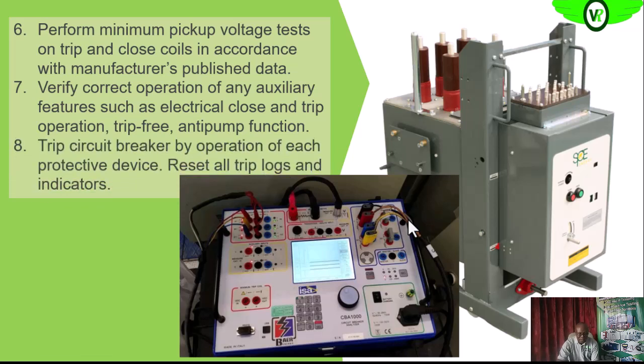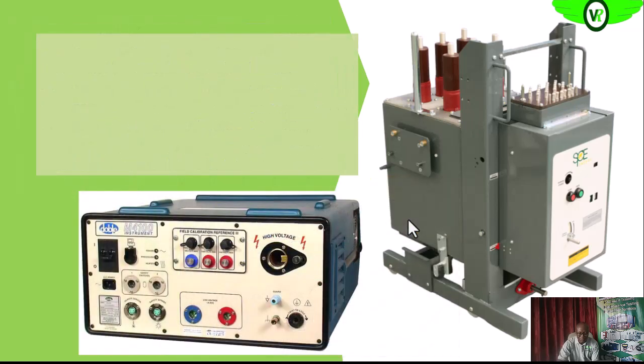Then next we can look at the trip circuit. Okay, so we want to operate the protective device to see that the trip circuit will actually respond. So all of those we can simulate some fault condition with the circuit breaker analyzer to see that the circuit breaker will actually trip when such condition is present. So the logs that we have in the protection, we can download them, and then if possible we can reset all the trips log, or we just leave them in the memory. Okay, and then if there are the ones that will prevent the equipment from functioning properly, we want to reset the equipment back to the factory, that is back to what we feel is normal for our operations.